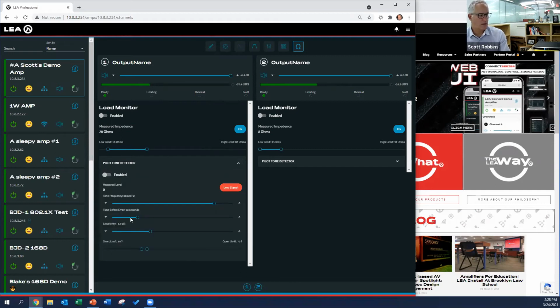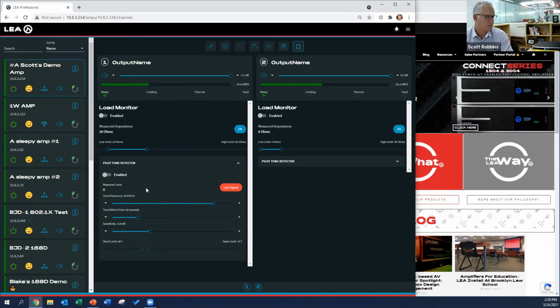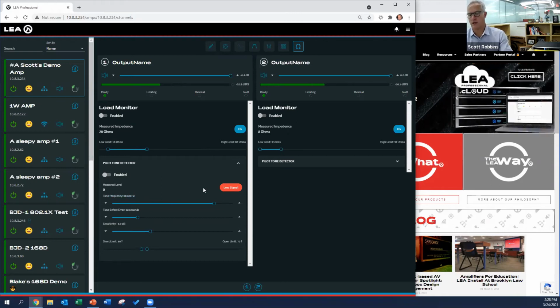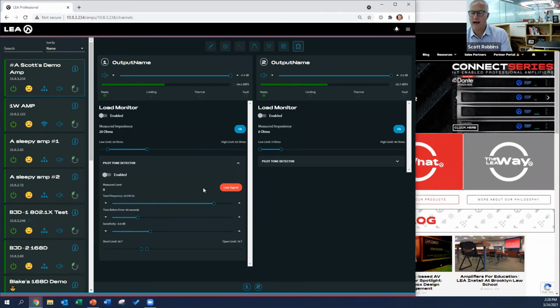The other load monitor is pilot tone detection. This is not dependent on program content. Here we're sending an inaudible tone, anywhere from 18 to 22 kilohertz, down the speaker line, and looking for a very specific impedance at that frequency. This is just a lot more accurate kind of load monitor, and it monitors the speakers 24/7.